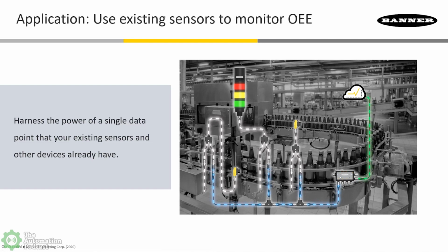We're harvesting a bottling application where they have some discrete sensors already installed, already talking to their PLC or control system. We're just using that data that's already there, using a parallel wired splitter, and converting that over to a unified serial protocol with those converters. The other branch of that splitter goes back to their existing control system, so the existing control system doesn't even see the converters or the other technology. It's an overlay, so it's not disturbing it in any way possible.